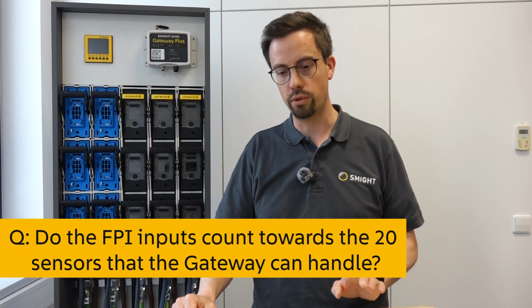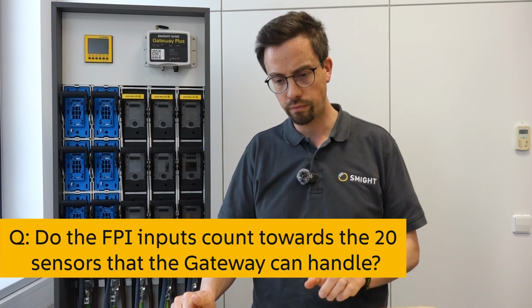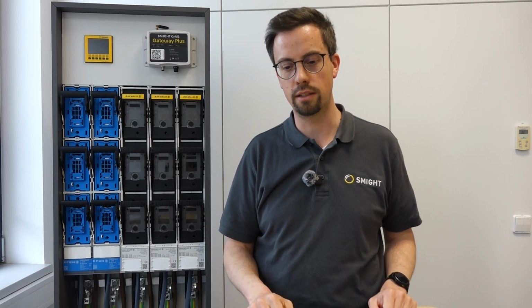The final question was, do the fault passage indicators count towards the 20 sensors that the gateway can handle? In our spec sheet, we state that our gateway can connect to 20 sensors. What we're referring to there are Bluetooth sensors - our feeder sensors for current, our voltage sensor, or the Bluetooth dongle for the Janitza devices. That's what counts towards the 20. Other inputs come through a direct wired connection to the gateway and don't count towards that 20. So you can have up to 20 Bluetooth connected sensors, and additionally the fault passage indicators or any other Modbus RTU connection.